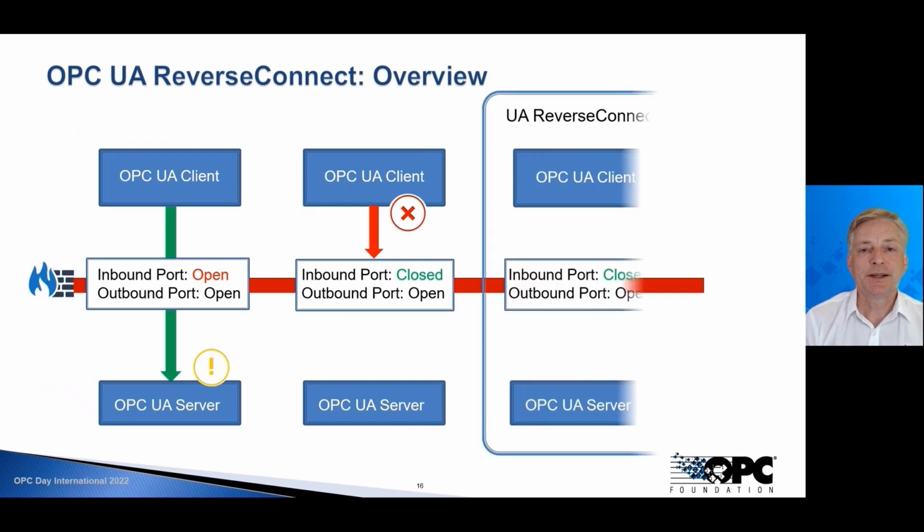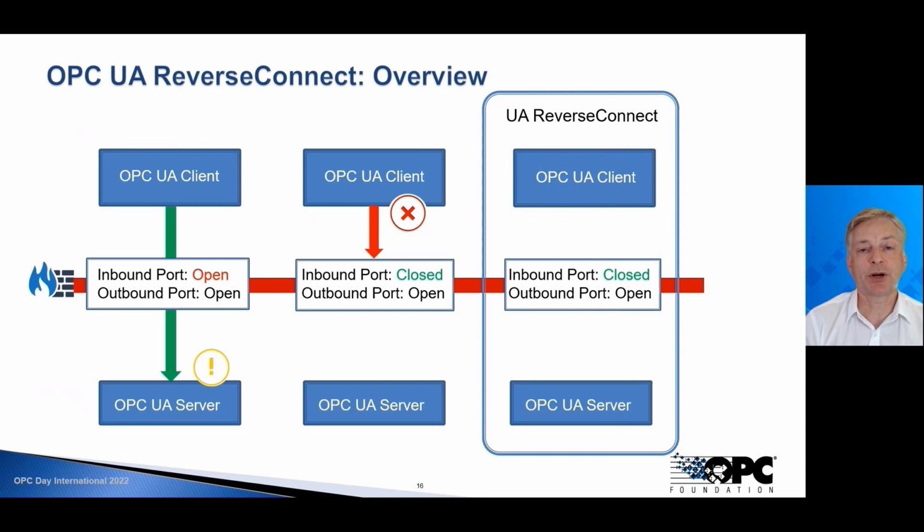doesn't work. So when you use OPC UA ReverseConnect, it is a two-step process. First of all, you have the OPC UA server call up to the OPC UA client, indicating that it wants to start a connection. By doing so, that connection is now open, and the OPC UA client then creates a secure session talking back down to that server.